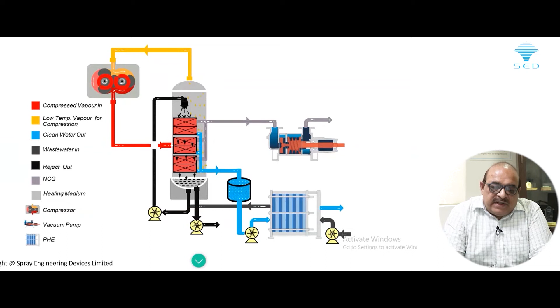and the vapors, we are creating a vacuum with the help of a vacuum pump, and non-condensable gases are being taken out with the same, and we create a vacuum in the system. Now, when this vacuum is created at this temperature, the boiling starts, and with the help of vapor we are taking it out and compressing it back to the system. Now, this complete system is the patent of SED, and with this particular system we are able to do the evaporation, get the condensate out, make the whole steam economy in one very compact system, and hence reduce the carbon footprint.